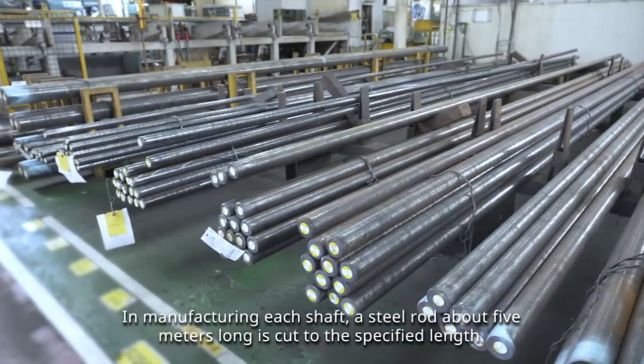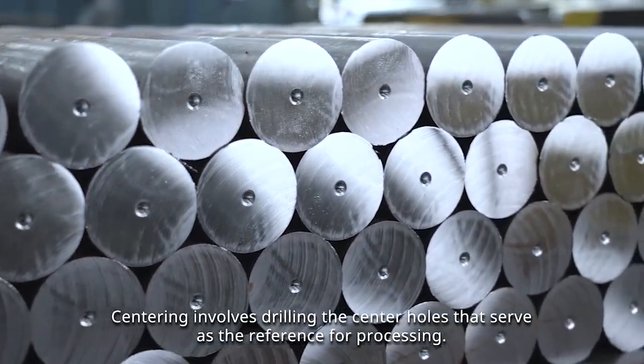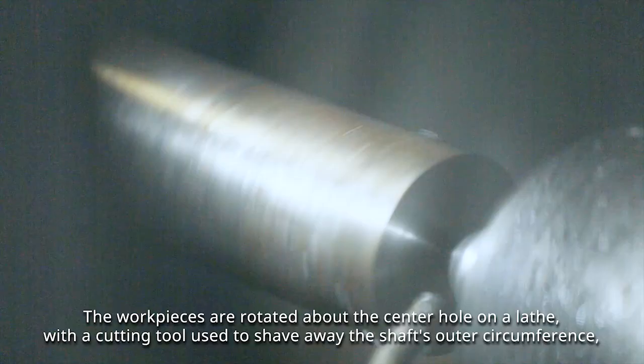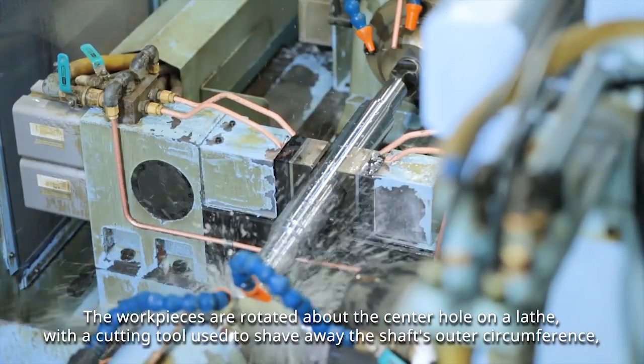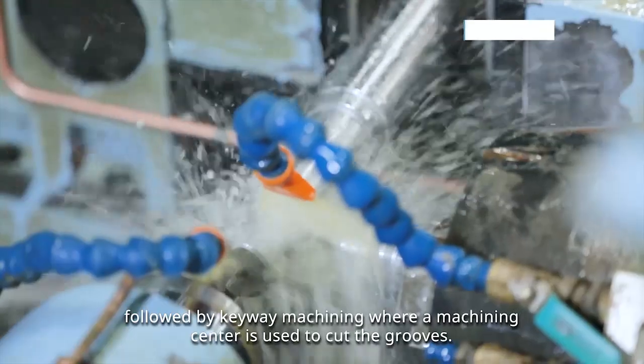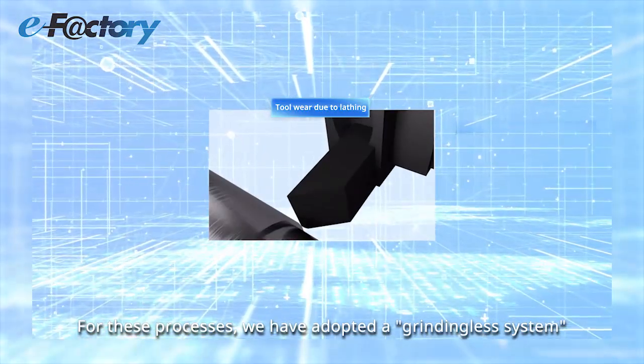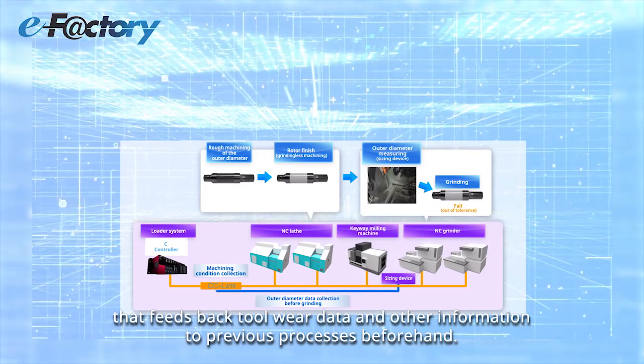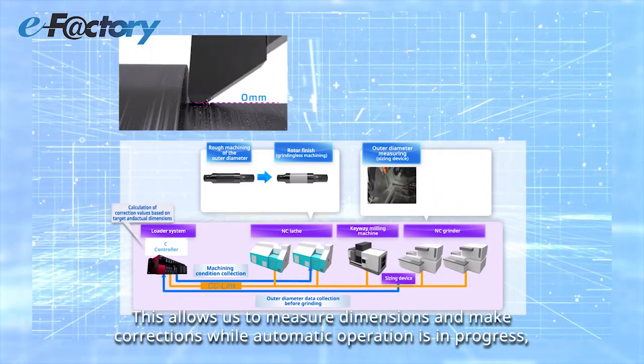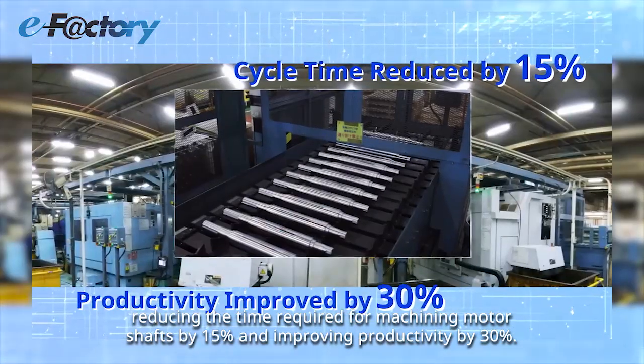In manufacturing each shaft, a steel rod about 5 meters long is cut to the specified length. Centering involves drilling the center holes that serve as the reference for processing. The work pieces are rotated about the center hole on a lathe with a cutting tool used to shave away the shaft's outer circumference, followed by keyway machining, where a machining center is used to cut the grooves. We have adopted a grinding-less system that feeds back tool wear data and other information to previous processes beforehand. This allows us to measure dimensions and make corrections while automatic operation is in progress, reducing the time required for machining motor shafts by 15% and improving productivity by 30%.